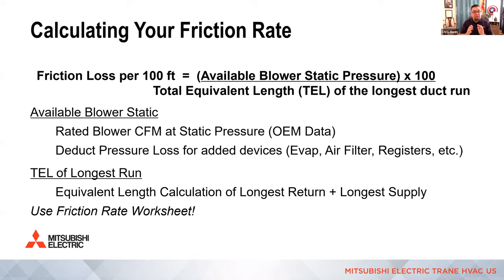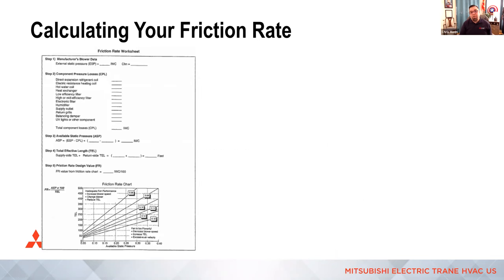All right. So in order to do this, yesterday all the attendees were sent two PDF copies. One of them is the friction rate worksheet, and the other one is the duct sizing worksheet. The first piece I'm going to walk through is calculating friction rate, or the friction rate worksheet. And I personally like the one that was taken out of the old Manual D, just because there's a great chart at the bottom. This chart will tell you what you need to do if the friction rate that you calculate is too low or too high for normal residential duct design. So that's why I like using that one.